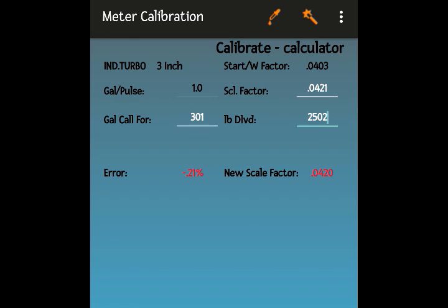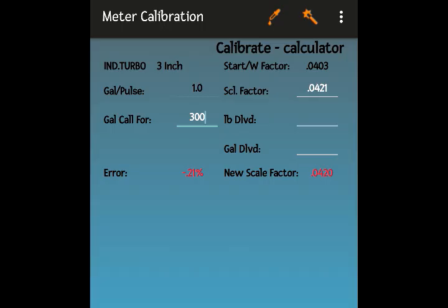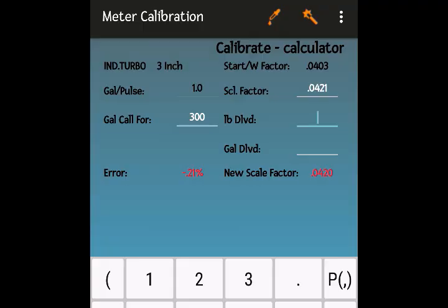In our third test here, we attempt to call for 300 gallons as always in the past two tests, and just happen to receive 300 gallons on our counter this time. So I'm going to change our 301 to 300, and we have weighed our results, and we end up with 2,502 pounds.